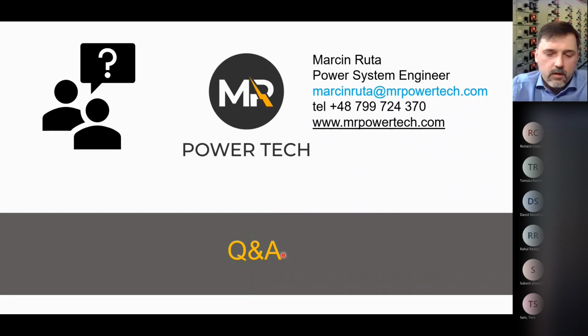On the other hand, they also added in the last revision that if you did any maintenance on your switchgear and your equipment, especially on the breaker, and now you are going to energize it, so after bigger maintenance, they consider this a higher risk, and they will tell you that yes, you need to have your PPE now. Despite this being normal operation, it's a bit higher risk, because if something goes wrong, it will go wrong in this way.